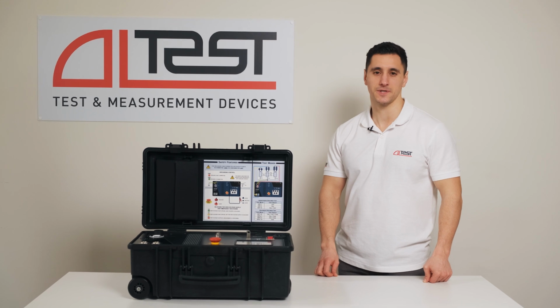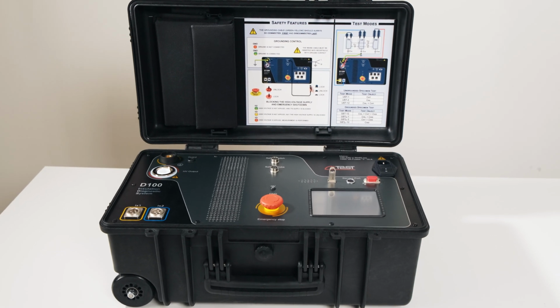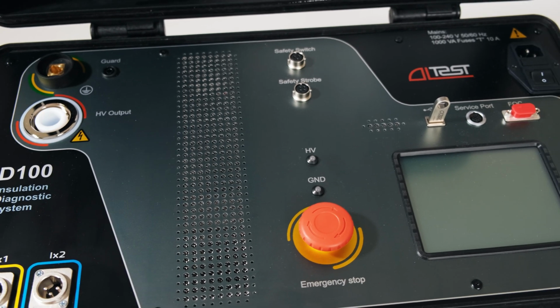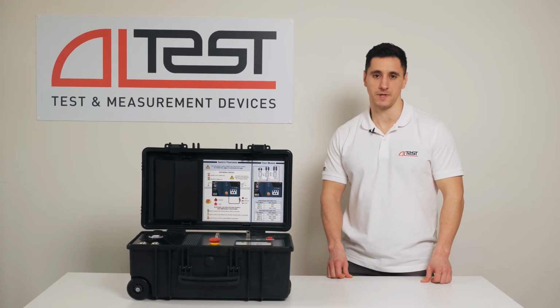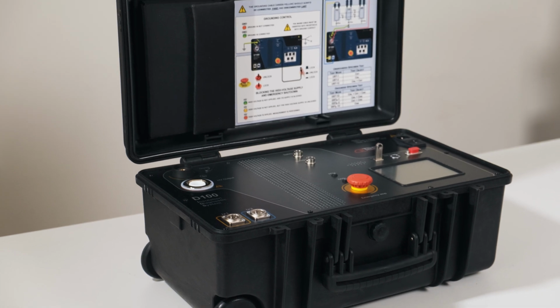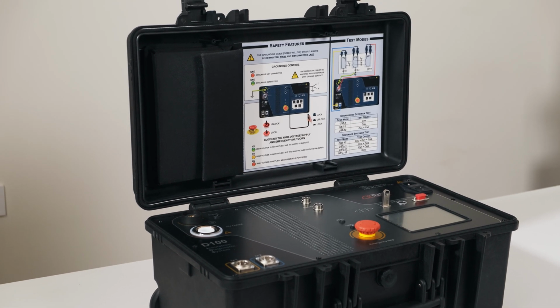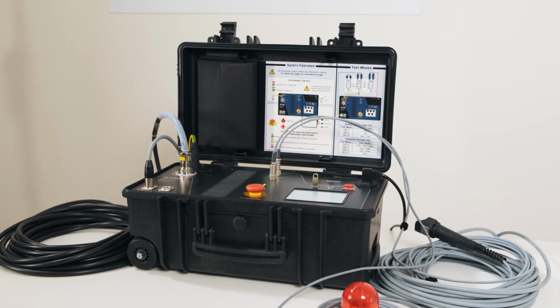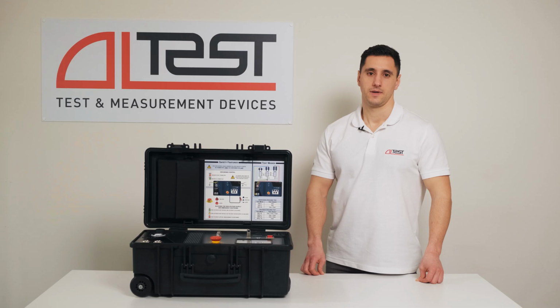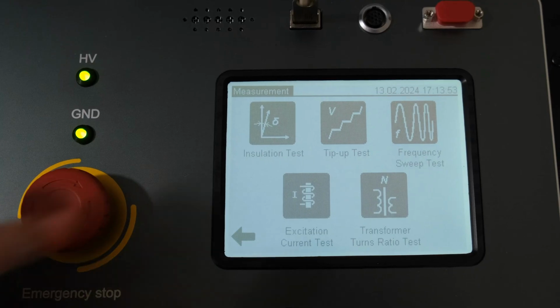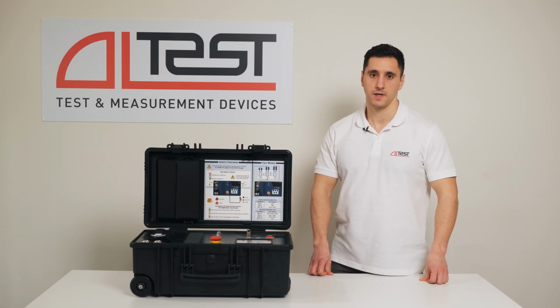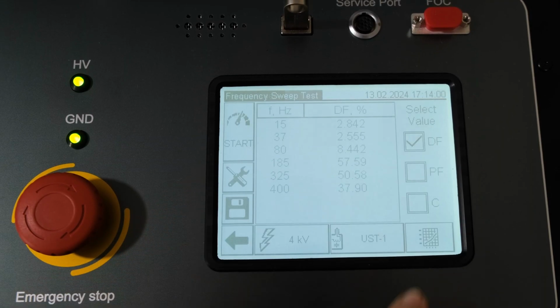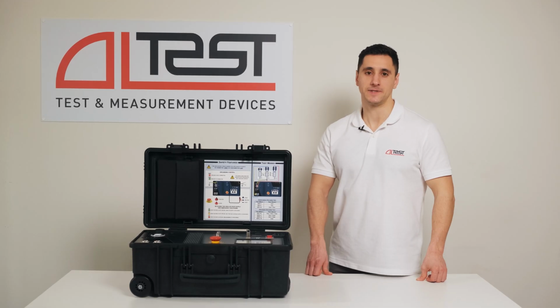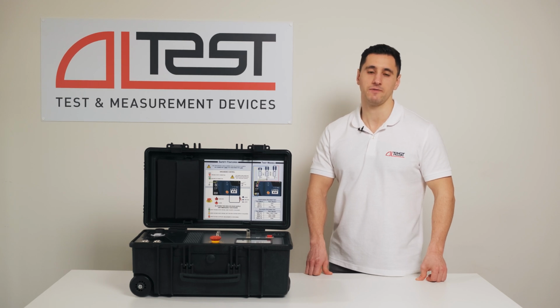This video demonstrates the new Insulation Diagnostic System D100 device. D100 is designed for testing power transformers and reactors, instrument transformers, bushings, high-voltage breakers, arresters, and capacitors in factory and field conditions. It measures the tan delta or power factor and capacitance. With the device, you can also measure the dependence of insulation parameters and voltage or frequency, the no-load current, and the transformer turns ratio when using an additional capacitor.